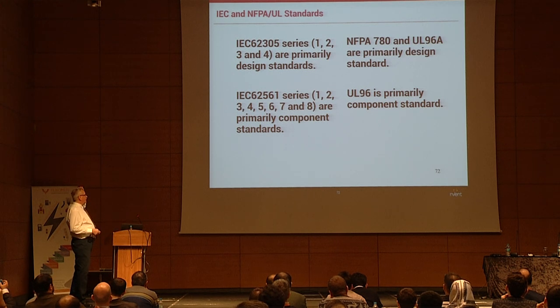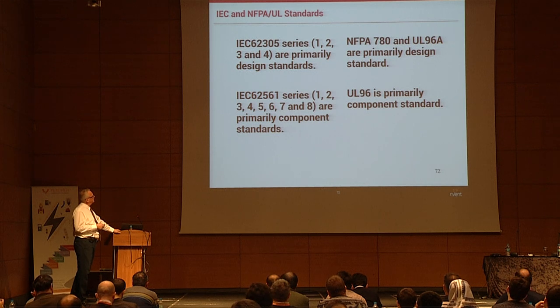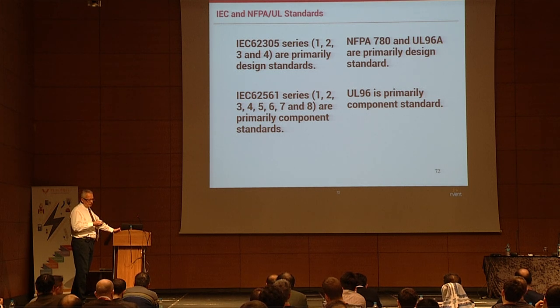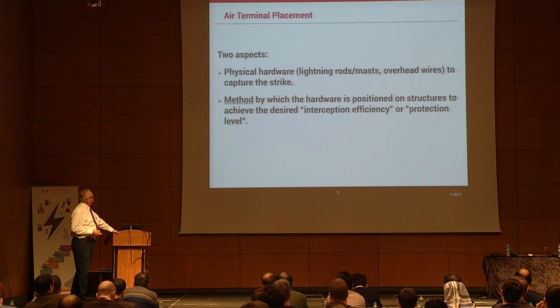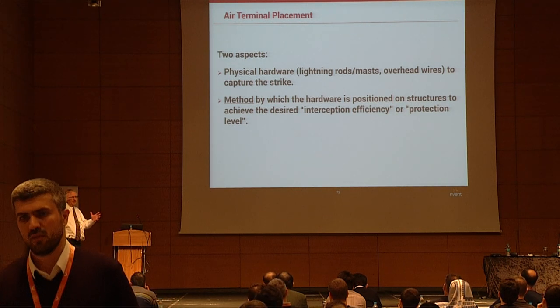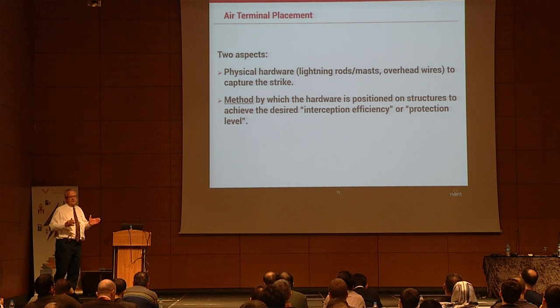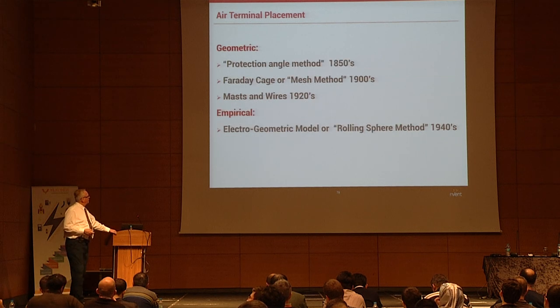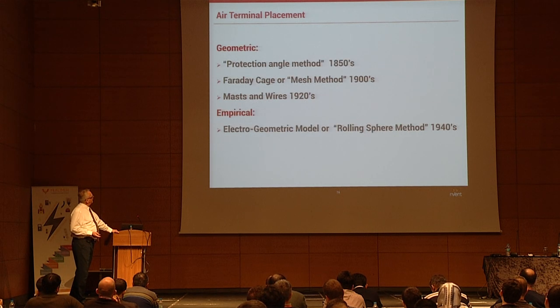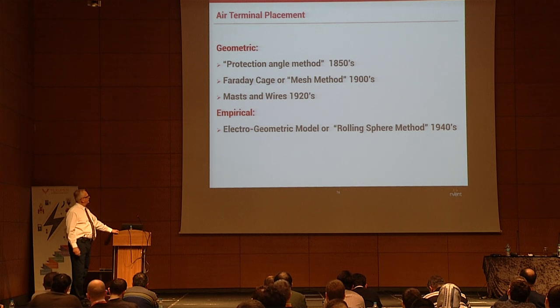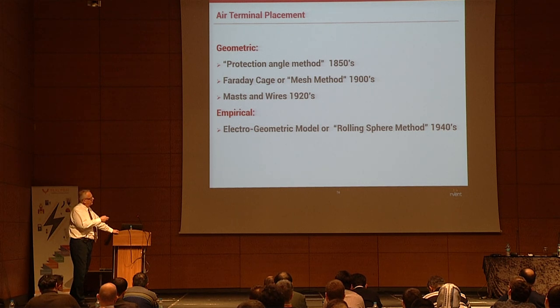Comparing IEC and American standards: NFPA 780 is the most popular method in the US and it matches the IEC standard. Lightning protection has two aspects — physical hardware (terminals, wires) and the method for placing terminals on the structure to get proper protection. Protection angle method was invented in 1850, mesh method in the 1900s, mast and catenary wires in the 1920s, and the electrogeometric rolling sphere model in the 1940s.